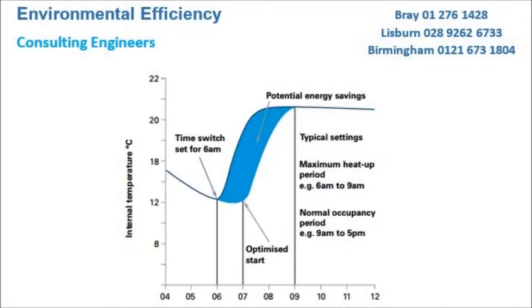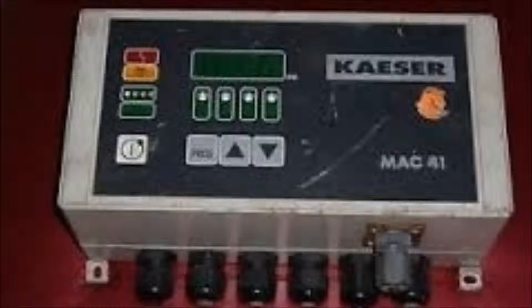Significant savings, perhaps up to 10% of the heating bills, could be made using these controllers. A good example of improved controls in industrial applications is the improved sequencing of air compressors. The traditional method of bringing additional air compressors online by pressure differential is extremely wasteful.